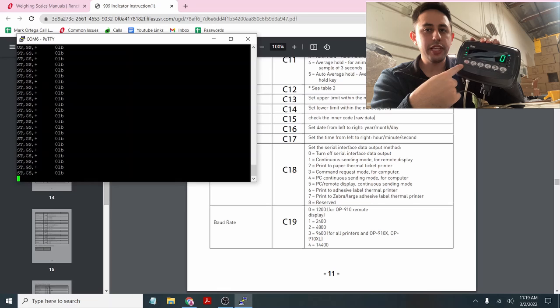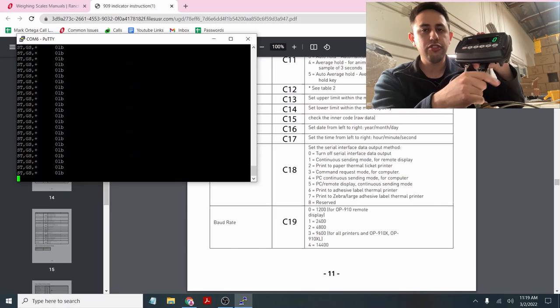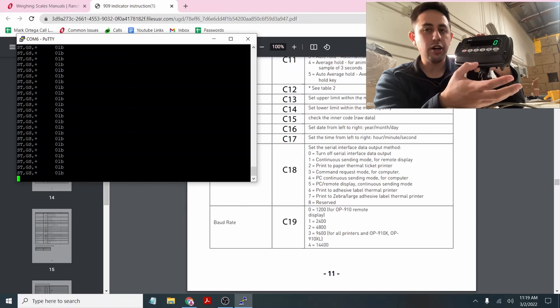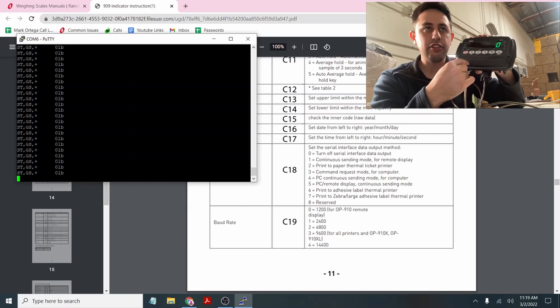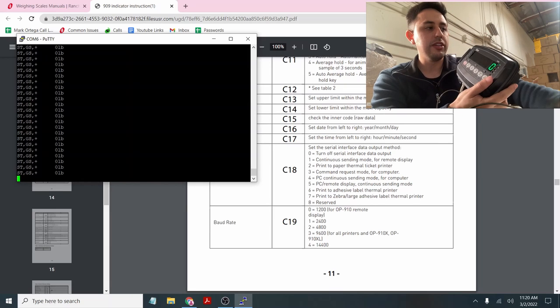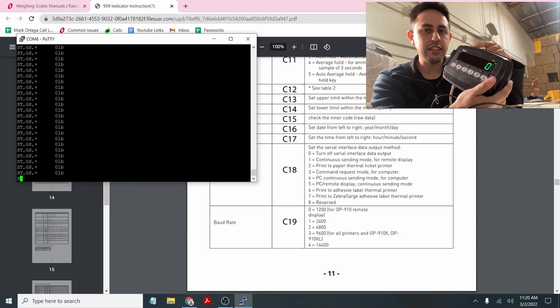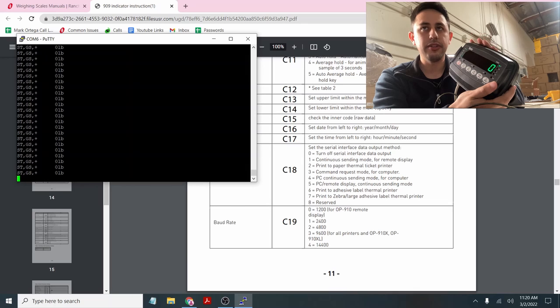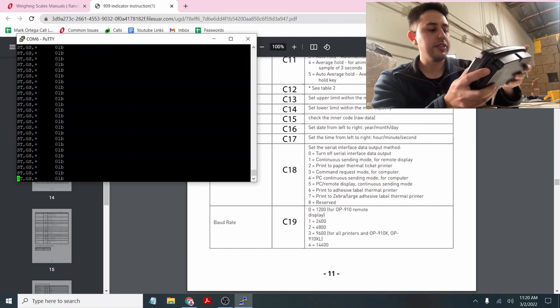Just realize that this is one-way communication, meaning this device is going to output through the RS-232 to USB to program. Whatever COM port software or PuTTY or whatever you're using, it's going to continuously output. If you send a command from the computer to the device, it's not going to do anything. I mean, I could type in capital R, capital T, I could do anything. It's not affecting this device at all. It's not commanding, it's not controlling. On the previous C183, I'm able to send a command to tare, and it will tare out whatever's on the scale. This one doesn't. It will just output one way. Some people that's fine, some people don't want it, it's up to you. So next one will be C185. So you see for PC, remote display, continuous sending mode, very similar.